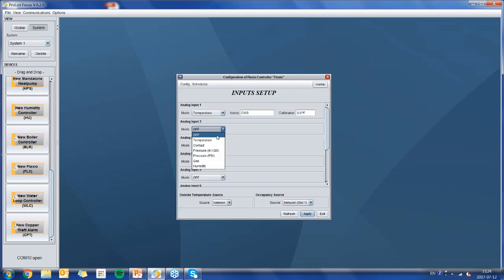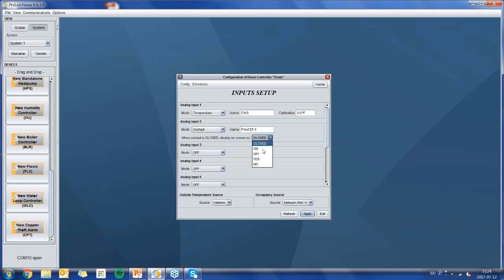So I'll go into the inputs, and this one is simply going to be a dry contact. I'll call it Proof Exhaust Fan 1. We can choose what is displayed when the contact is closed - yes, no, on, or off. Since it's called proof, I'd want to say yes - do we have proof, yes or no?